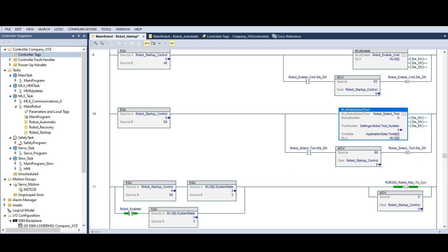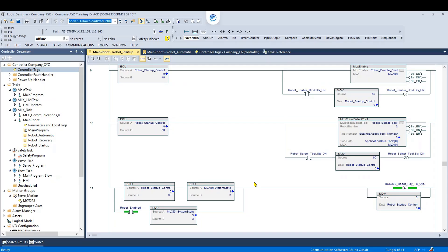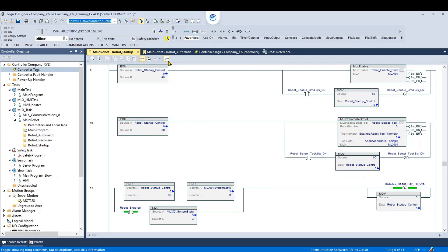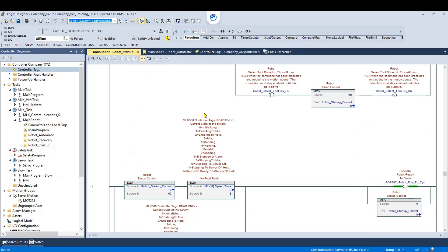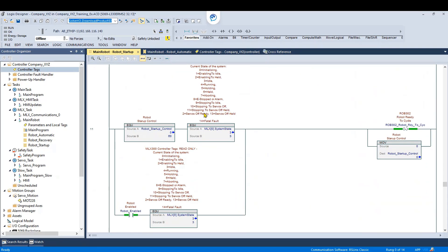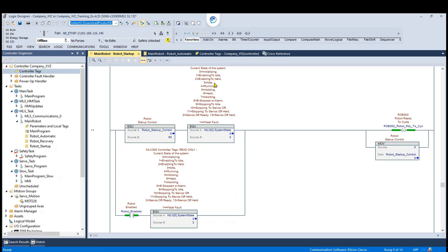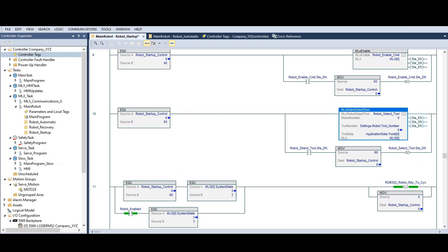On this step, it's checking for the system state to be equal to 3. If you press the toggle documentation button, you will see that system state 3 is idle. The idle state means that the servo power is on and the robot is waiting for a motion command. When this is true, the robot ready to cycle signal will be latched on and the startup step will be set to zero.